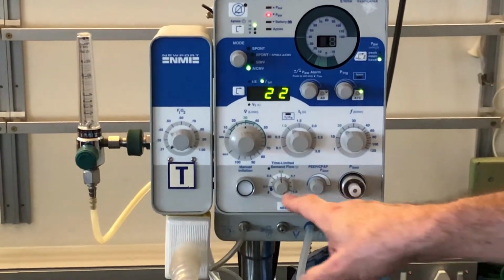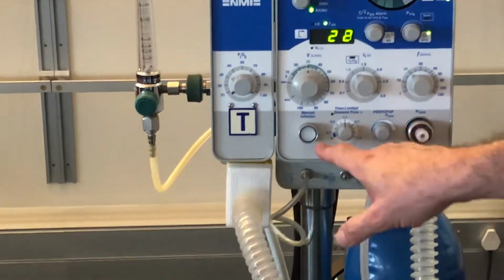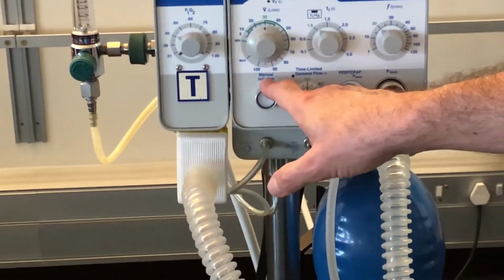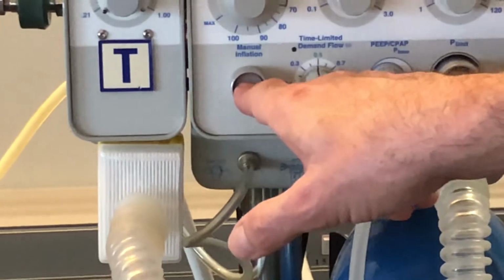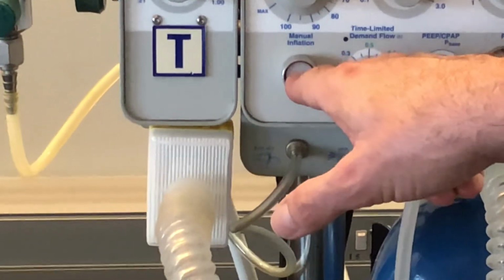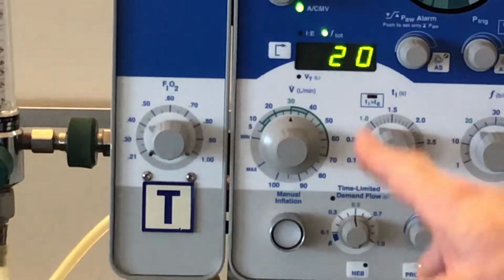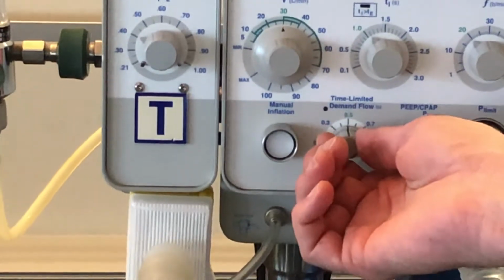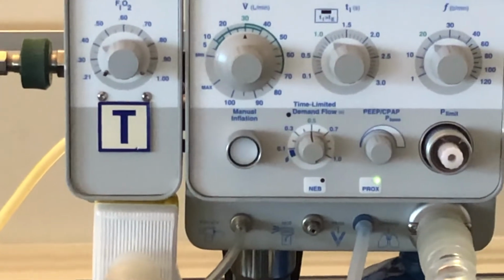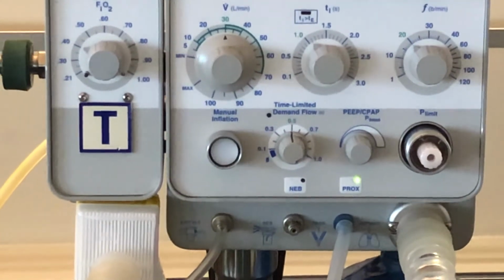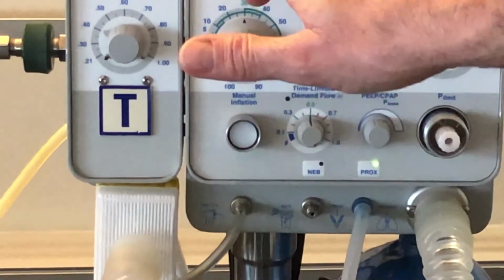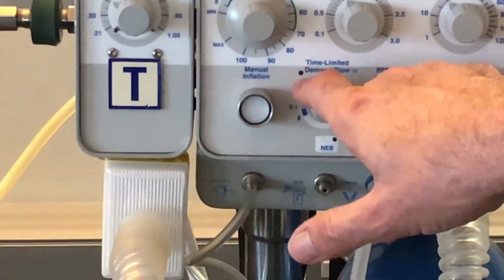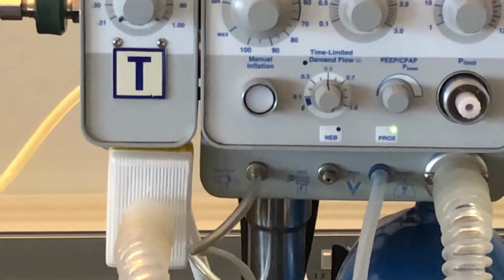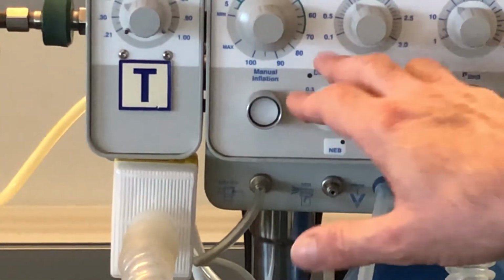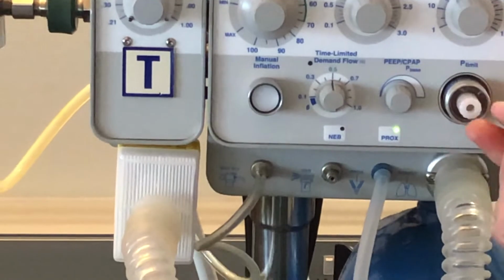And then just to go through some of the last details on the bottom row, the first button here says manual inflation, and all that will happen is every time I push the manual inflation button in any mode, the machine will deliver a preset breath. The next setting here is the time limited demand flow. So time limited demand flow is not active in assist control ventilation. You'll see there's no light on there, and when we choose a mode in which it's active, I'll explain it to you.